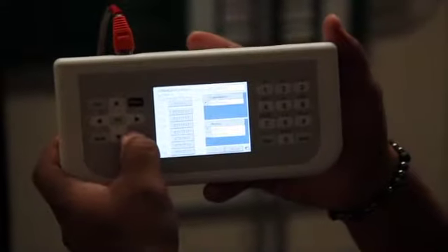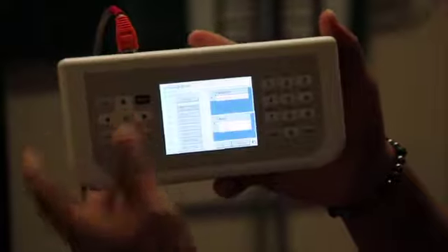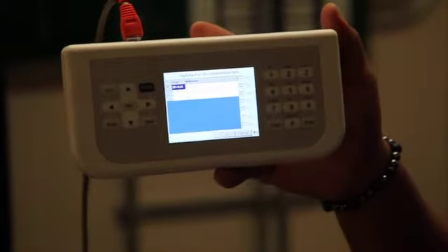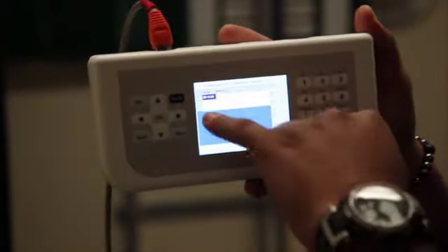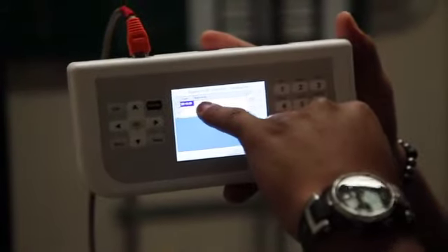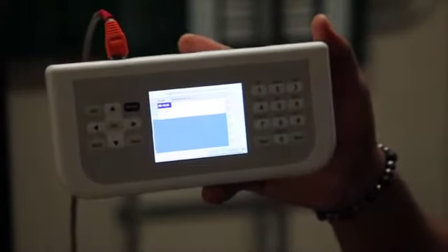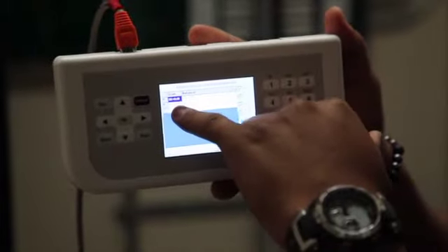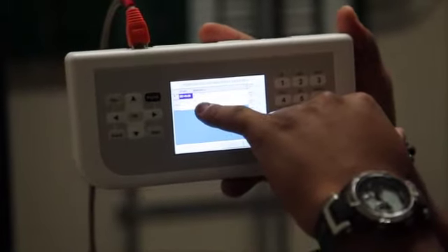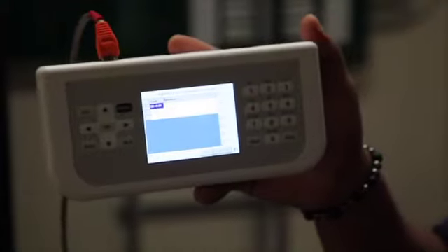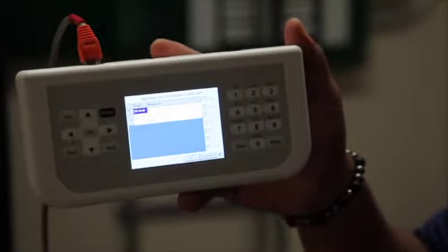Okay. So if I go to Monday and select OK, I have two instances for the schedule. I have a sunrise plus 10, which is off. It's telling me 10 minutes after sunrise, lights are going to turn off. Then I have a sunset minus 10 at a behavior 6, which is on. So 10 minutes before sunset, lights will turn on.